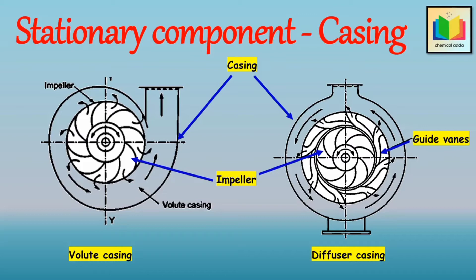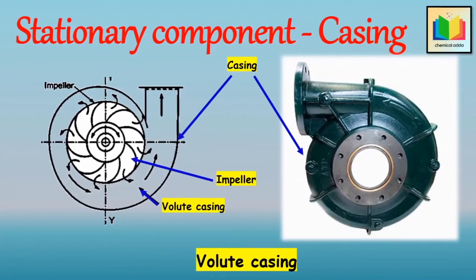Circular casings are used for low head and high capacity applications, but are seldom used. The second type is the volute casing, which builds a higher head. A volute is a curved funnel increasing in area to the discharge port. As the cross-sectional area increases, the volute reduces the speed of the liquid and increases its pressure. One main purpose of a volute casing is to help balance the hydraulic pressure on the shaft. The liquid discharged by the impeller enters a chamber of gradually increasing cross-sectional area toward the outlet, so fluid velocity decreases gradually, increasing fluid pressure. The volute thus converts kinetic energy into pressure energy, though some energy loss occurs due to eddy formation.